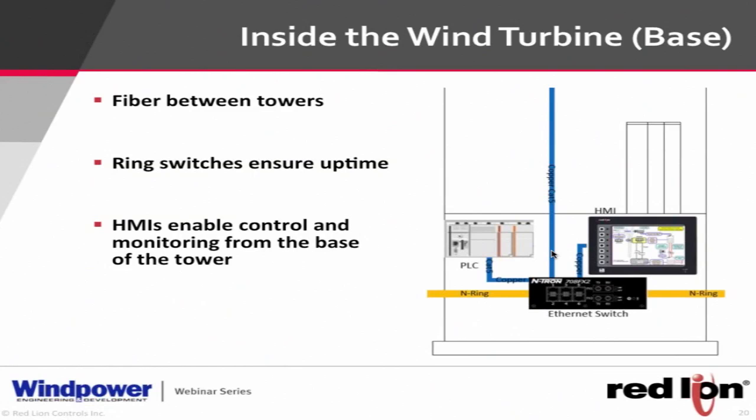Well, the problem with that, 1 to 3 seconds, is a lot of things can happen, and we need it to happen immediately. We need to know that these PLCs and these drives are communicating, and there's a scan time in it. We want to make sure we don't miss that scan time. And so we need a very fast heal time on our ring, and that's what N-Ring offers.